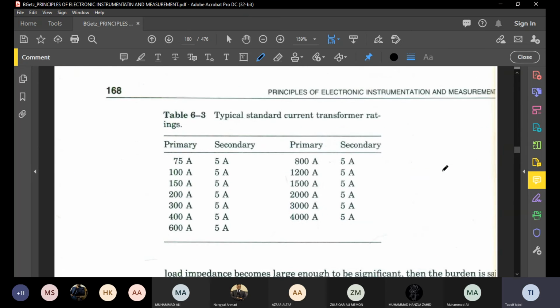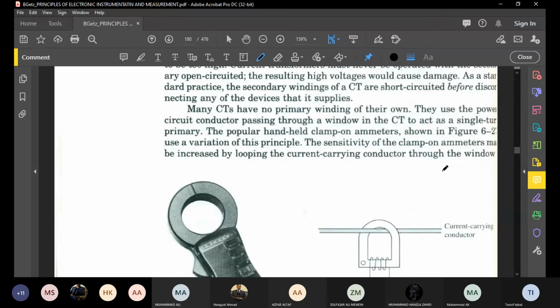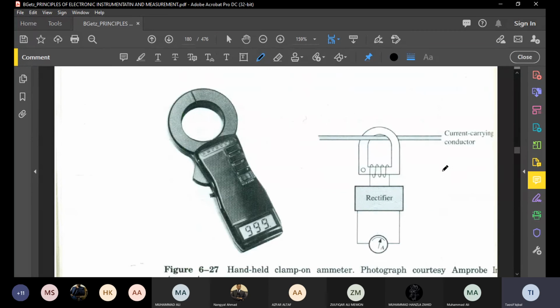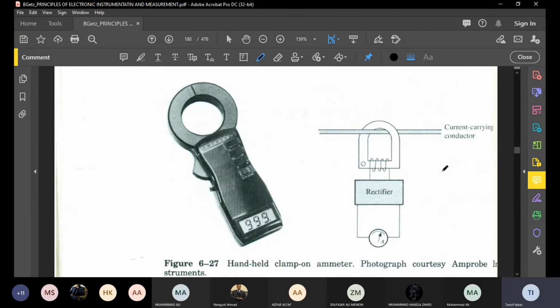And then we have a special kind of current meter called a clamp-on meter. In this, we basically have a core divided into two halves, and with the help of a button, we can separate the two cores. And when the button is released, we can hang it on, or clamp it on, a current carrying wire or conductor.